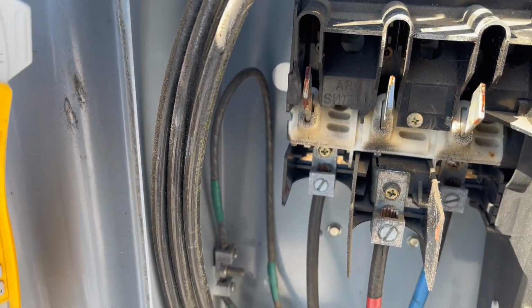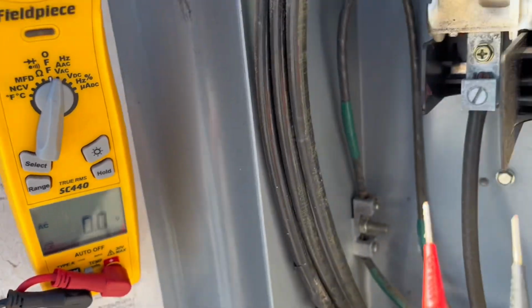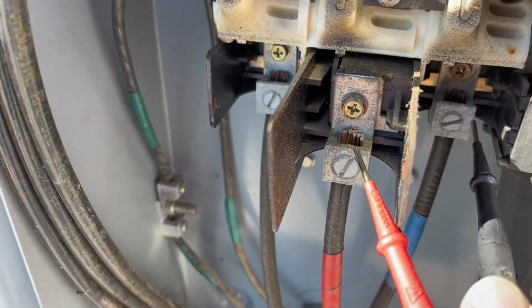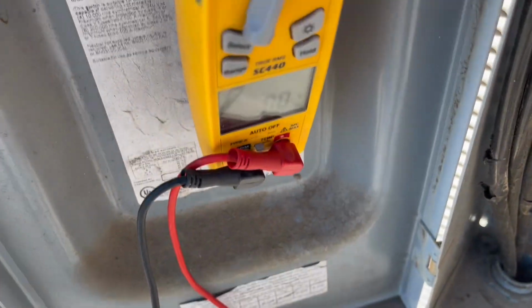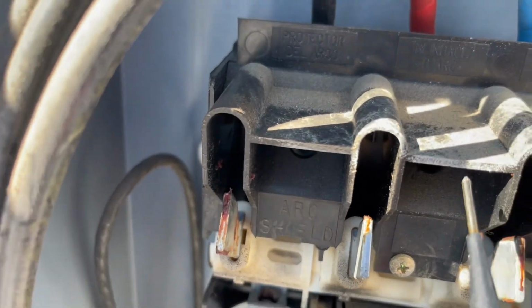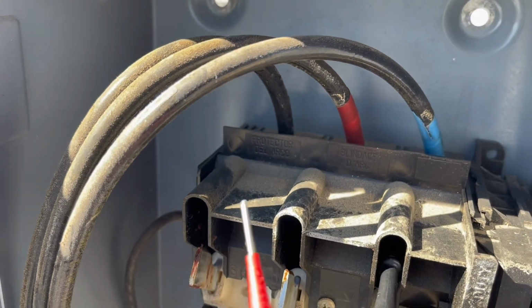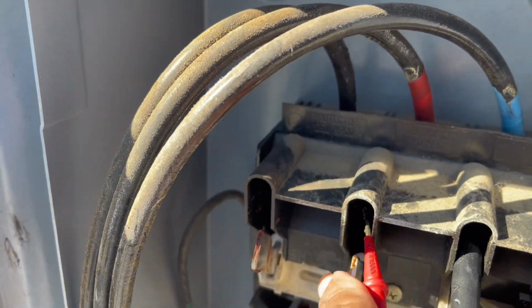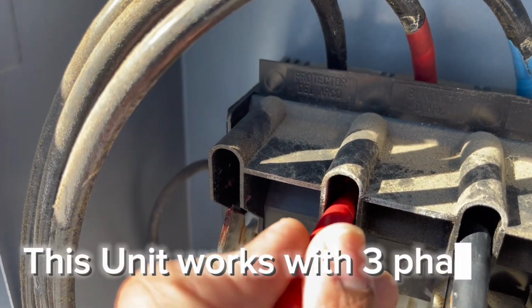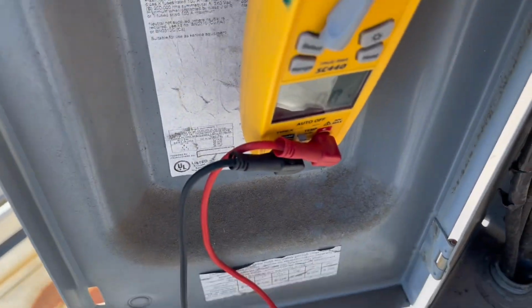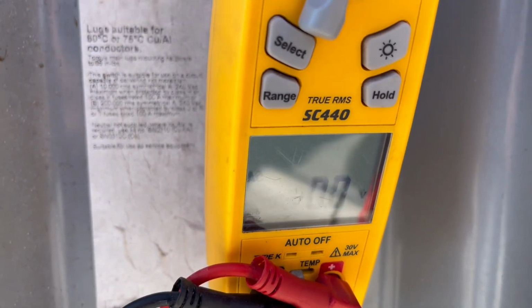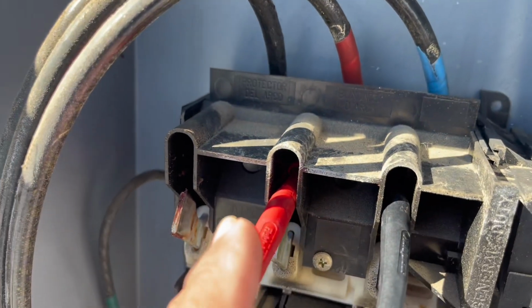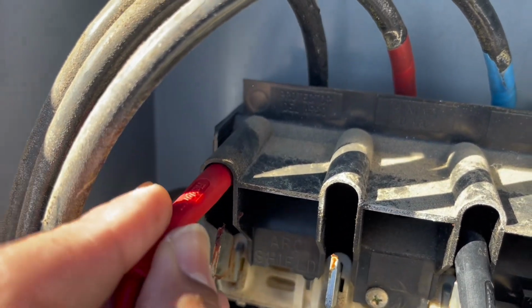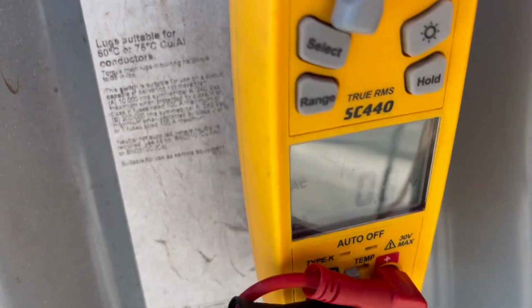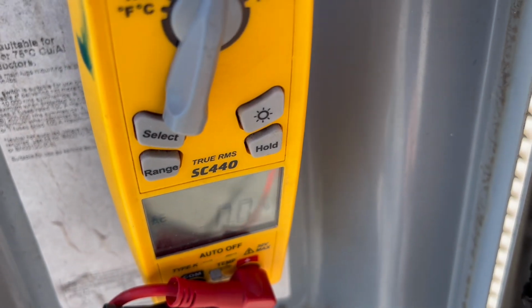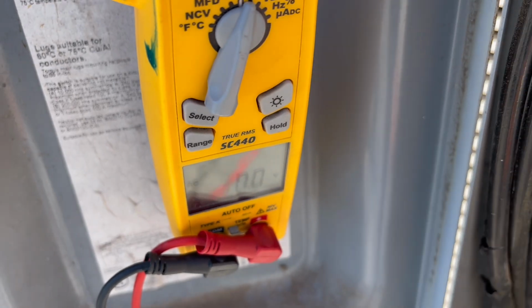Well, all indicates that we don't have power here. It is reading 0. I mean, this right here is a low, of course it's going to be 0. But if we check somehow here, our phases, we have 0 as well. There's no power at all. So no power, so we have to check this breaker panel and see what's going on.